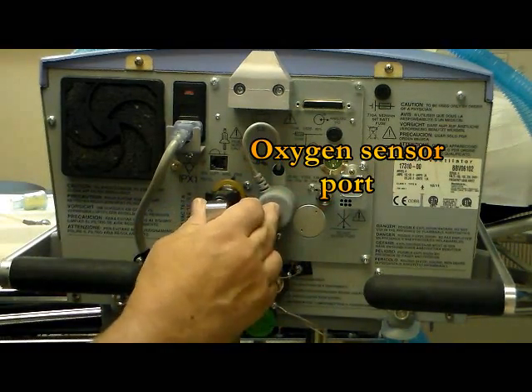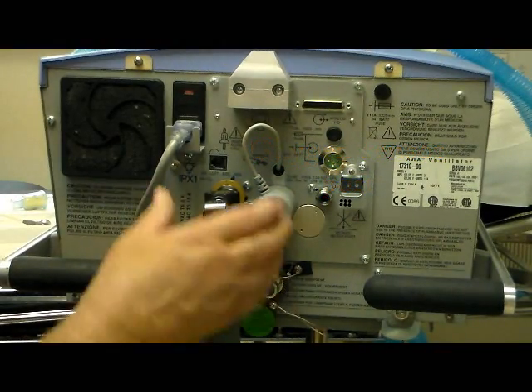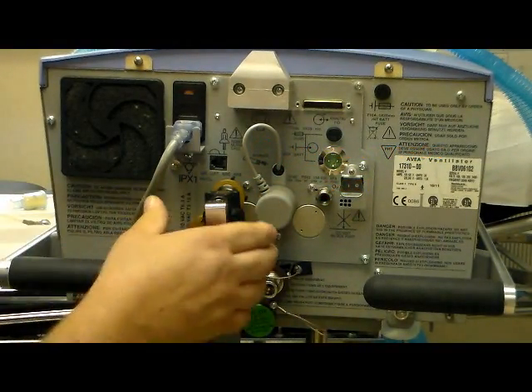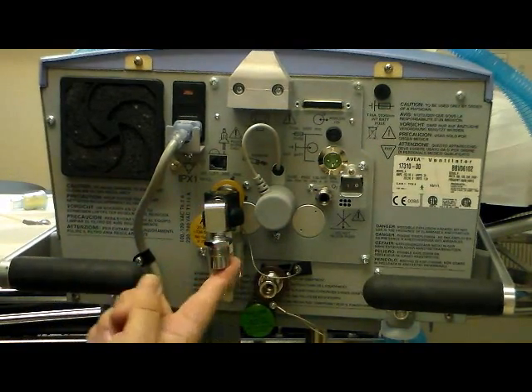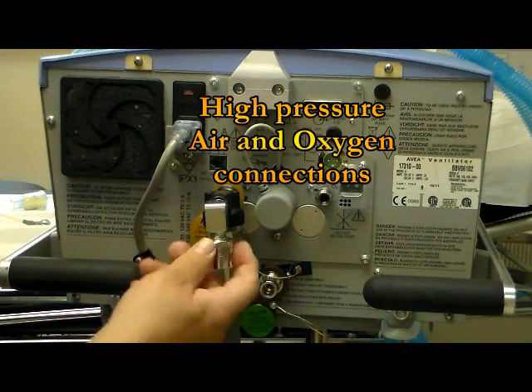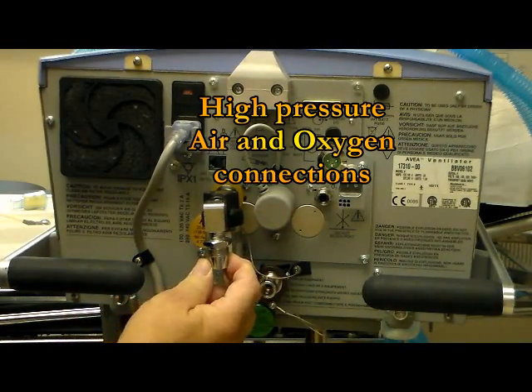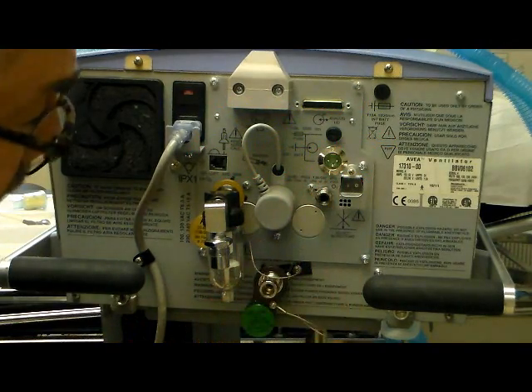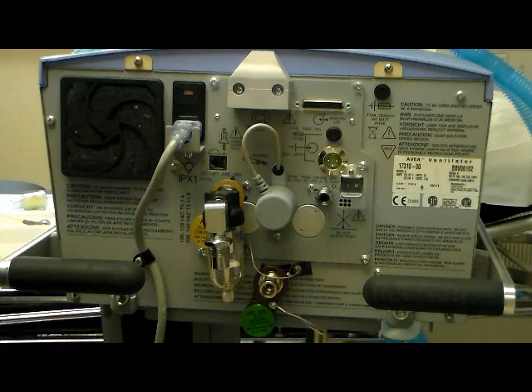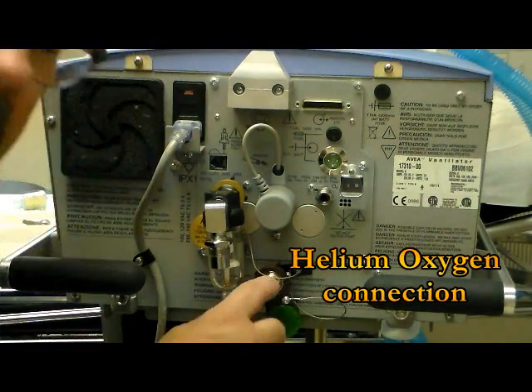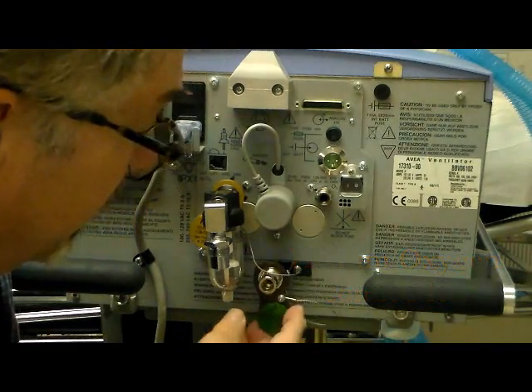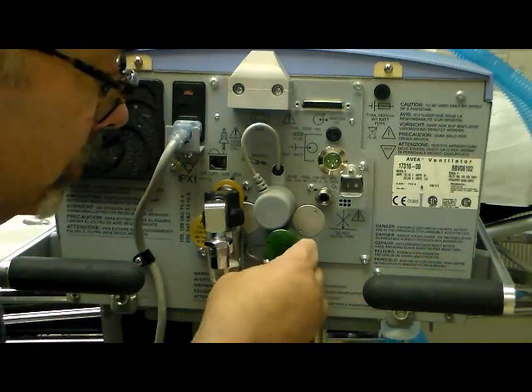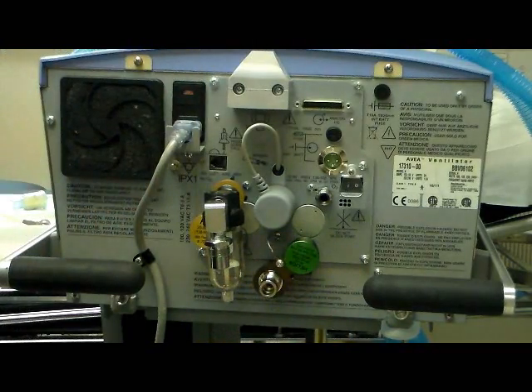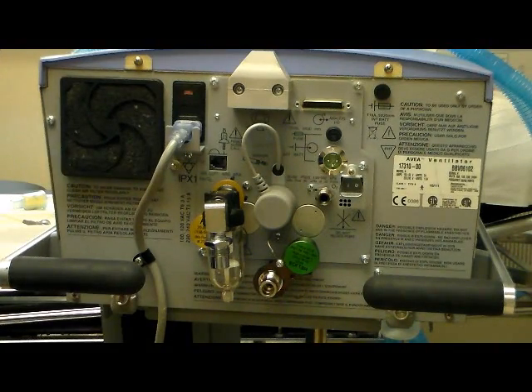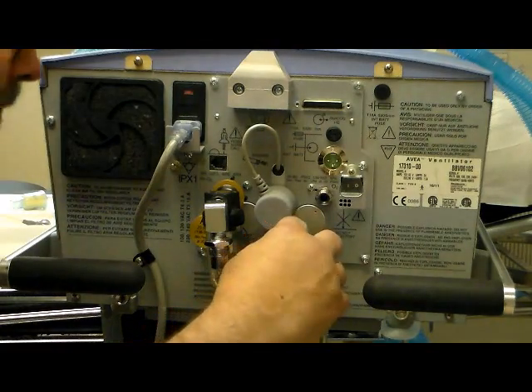We have an O2 sensor here that will measure the gas that we're giving the patient, so we're getting accurate measurements. And then we have the air high pressure tubing, high pressure hose connection here, the DISS fitting, and then the oxygen DISS fitting as well. Now, one of the nice things with this machine is that you have a helium oxygen port, and as soon as you connect this to gas, turn it this way, it will begin to calibrate the machine on helium oxygen measurements, so that you will get accurate helium measurements.